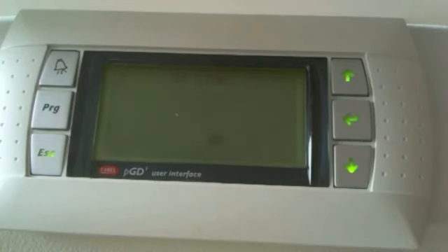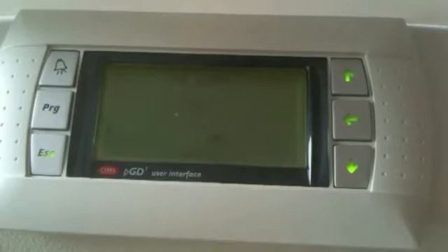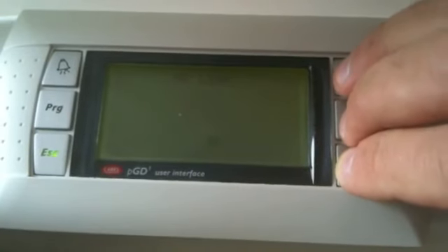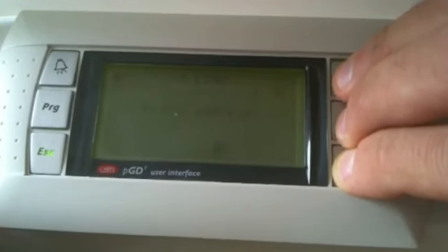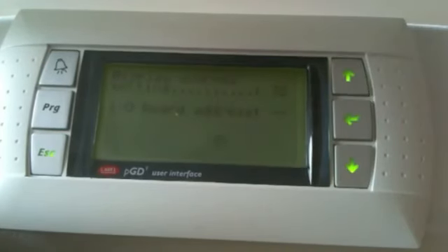The first thing I will do is temporarily set the address of the display to address 00. That is done by simply pressing the three buttons on the right-hand side together simultaneously until a new screen appears. You will see the cursor blinking on the top left-hand side with the ENTER button. Move the cursor to the next modifiable field and bring the value from 32 back to 00, then confirm with address 0. The confirmation screen saying 'display address changed' will appear.